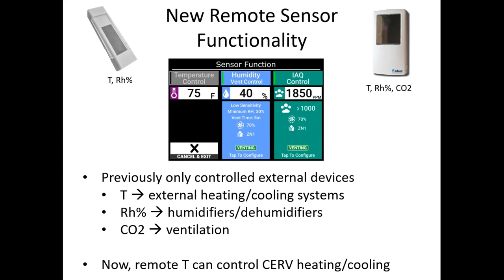Some new functionality for the remote sensors. Previously, the CERV could use the remote temperature, humidity, and CO2 sensors to trigger things externally. But now you can use the sensors to do internal functions on the CERV. The remote temperature humidity sensor is a combined temperature and humidity sensor. You can now use the temperature located somewhere else in the house to trigger the CERV's heating or cooling function, in addition to the built-in temperature that the CERV is reading from all throughout the house. So this would let you put it in some other space and tell the CERV to heat or cool based on what's going on there.